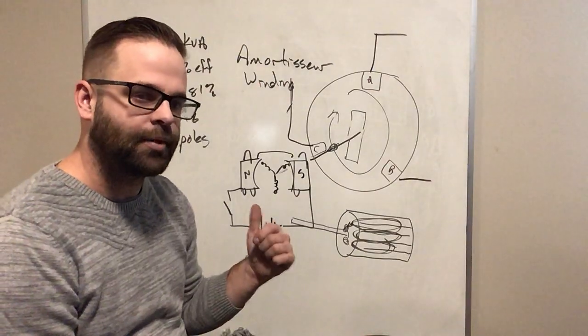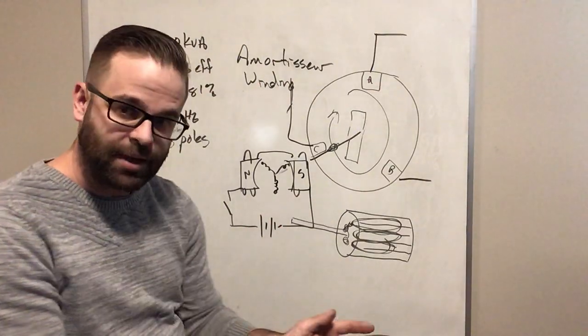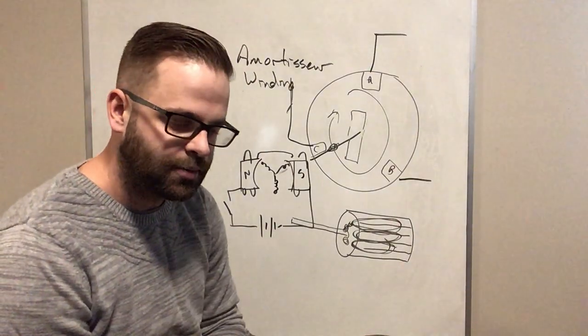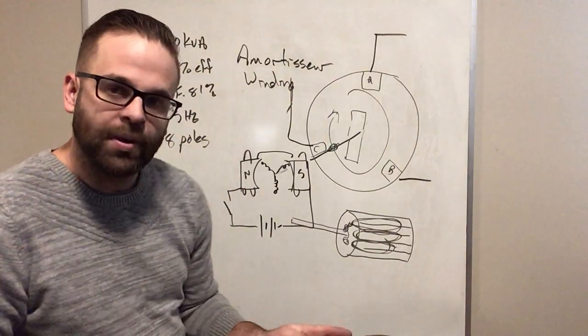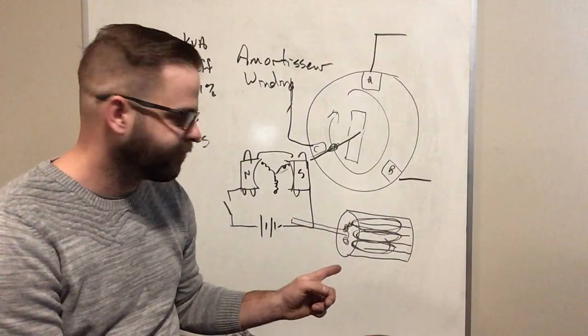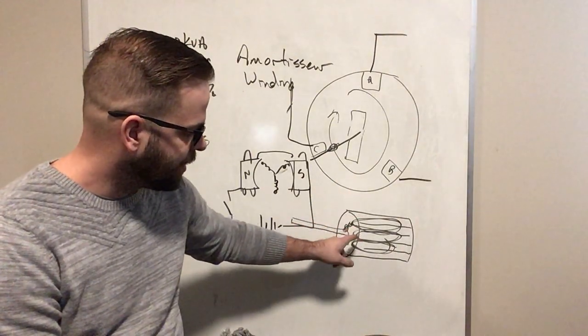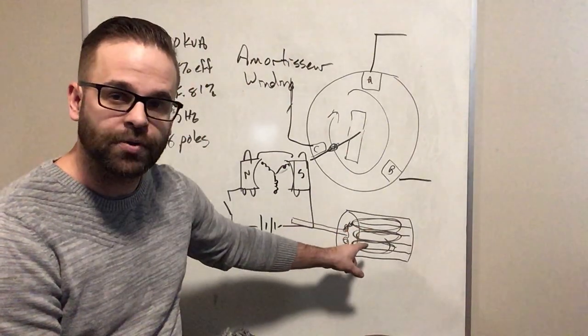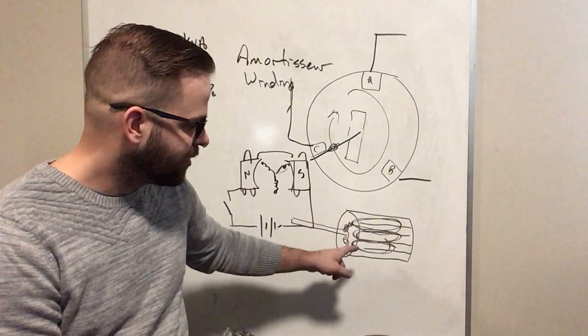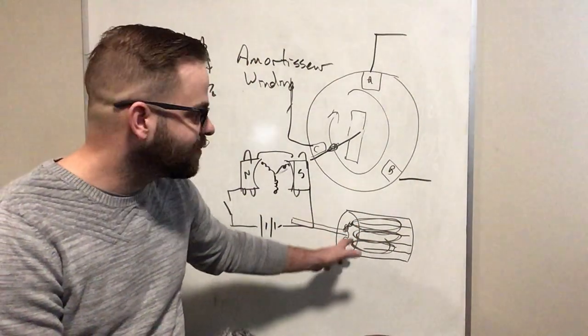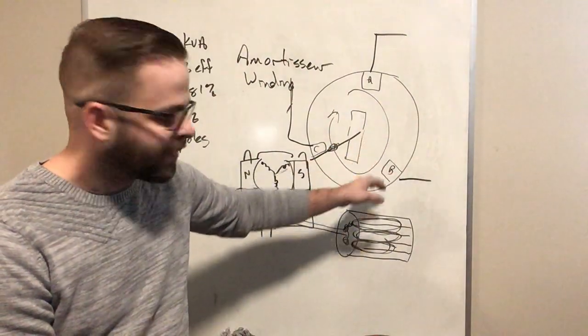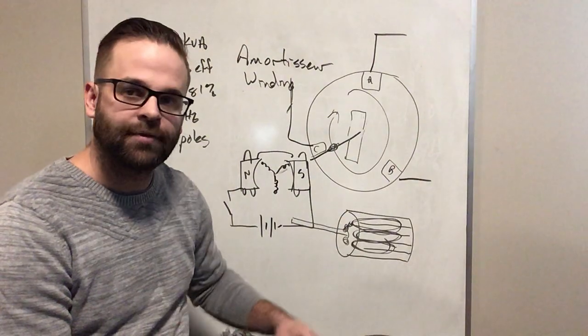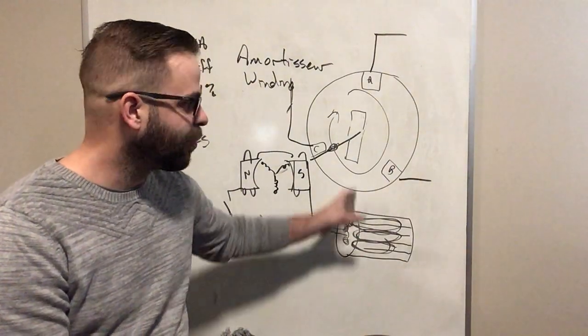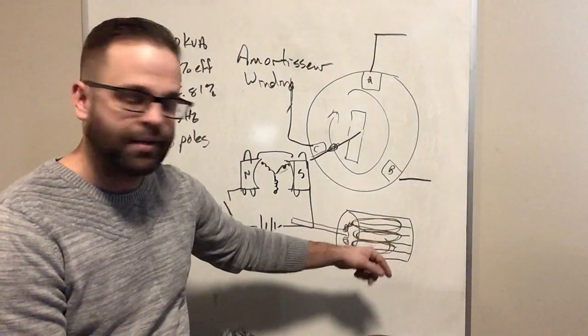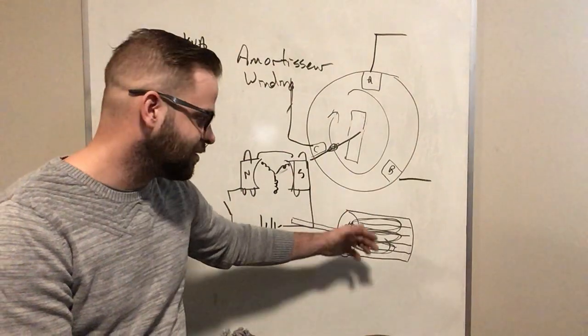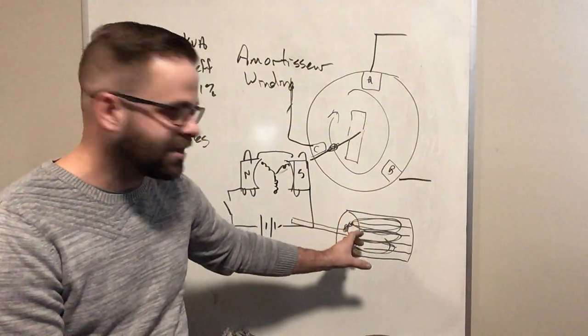So that's why when we go to start up the motors in the lab, we go to hit start. And remember, they kick up the speed, but they don't quite get up to synchronous speed. And the reason for that is I always need to have relative motion between my amortisseur winding and my rotating magnetic field. So this one might get up to 1,798 RPMs, while this one's at 1,800. And the reason why I need relative motion is if there's no relative motion, so if these are both the same speed, there's no lines of flux being cut. If there's no lines of flux being cut, then I don't induce a voltage, I don't induce current, and I don't create a magnetic field on the shaft. So this always has to be slightly slower.